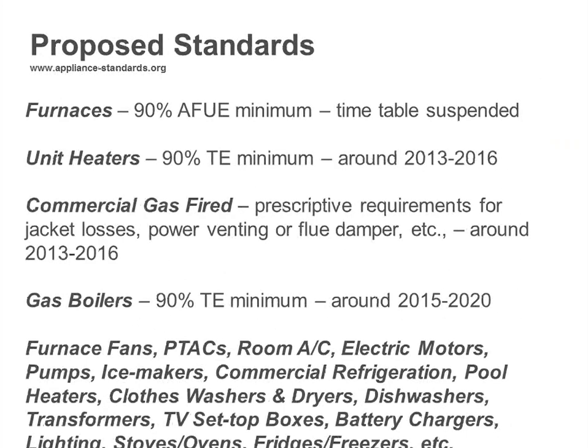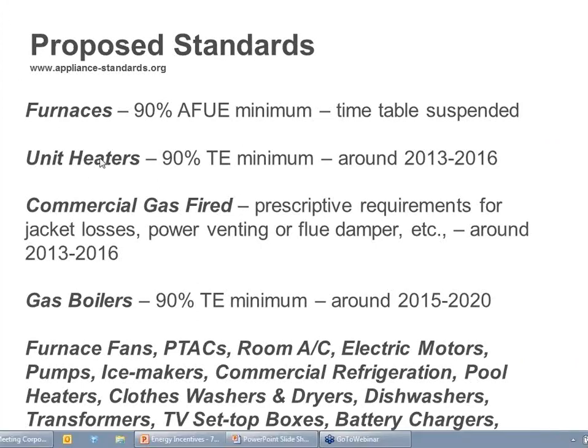There's lots of other things that are under scrutiny and current plans being drafted by the Department of Energy and or various associations in conjunction with the Department of Energy. So some of those things that you're going to start seeing changes on: furnaces when they finally happen, unit heaters, gas-fired boilers just had a change last September, but another 4 years or so or whatever it's going to be, you're going to see another boost in the minimum boiler efficiency, furnace fans. There's all kinds of categories that are getting picked on, if you will. So there's a bunch of changes happening there.